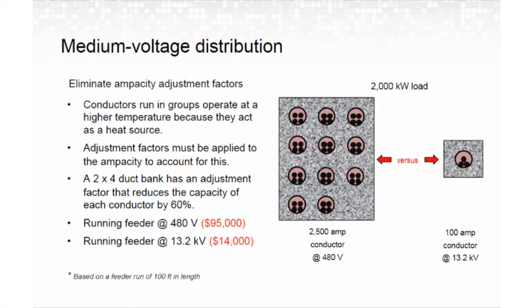Now, just for clarification, the third bullet point there should read a 3x4 duct bank has an adjustment factor of about 60%, since that's essentially the example that we're using here. Now, as with the previous example, a substantial amount of feeder cost savings can be had by using higher distribution voltages. Now, that said, distributing at higher voltages does require additional transformers, which you have to consider when you look at the whole system budget.